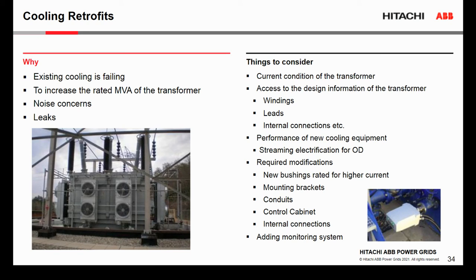Now I will talk a little bit about the cooling retrofits. So why do we have to do the cooling retrofits? Mainly because the existing cooling equipment is failing. We may have a problem with leaking radiators or fans or pumps failing. In some cases, we want to increase the rated MVA of the transformer. We have concerns with noise, so we want to change the coolers to new ones which produce much lower noise. And those are the main reasons why we do the cooling retrofits. What do we have to consider during the retrofits or before?